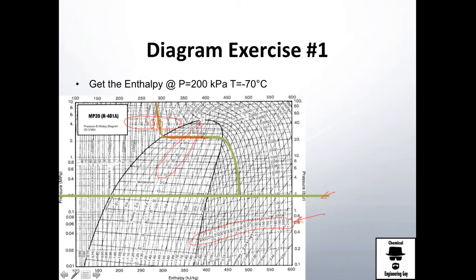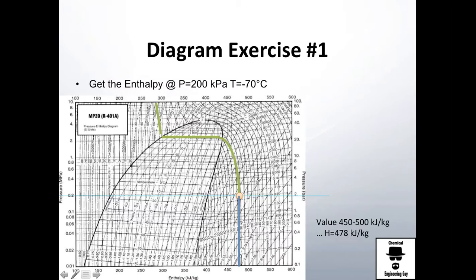Along this isotherm there's no change of temperature, and then you locate the intersection point. This point right here is the point we're looking for. To read the enthalpy, go directly down to the x-axis — I get something between 450 and 500, specifically 478 kilojoules per kilogram, which is the answer to this problem.